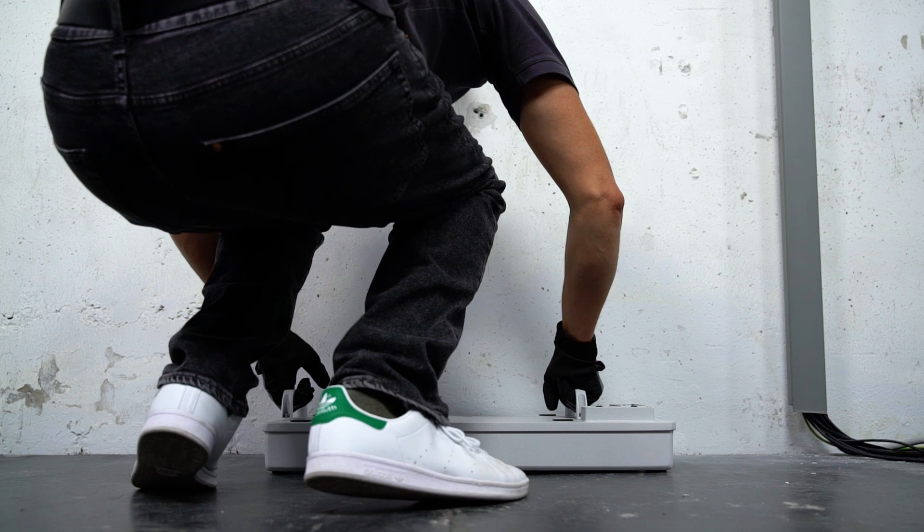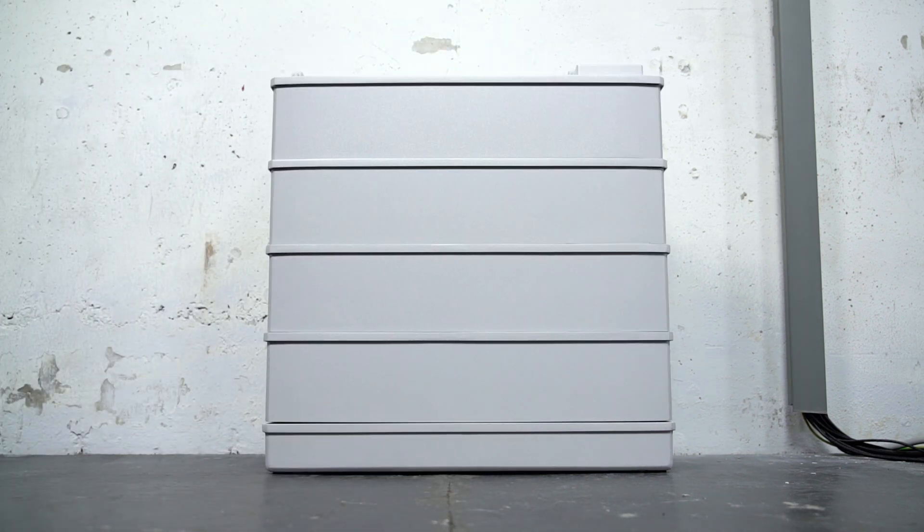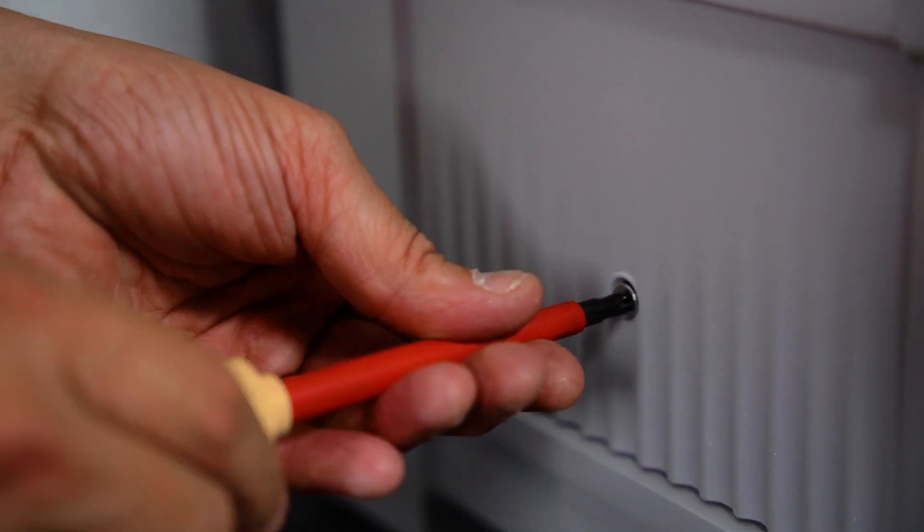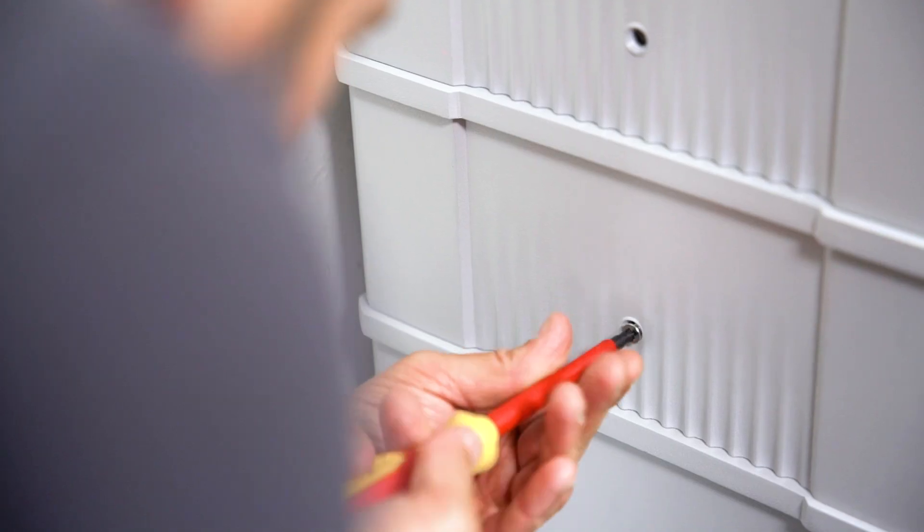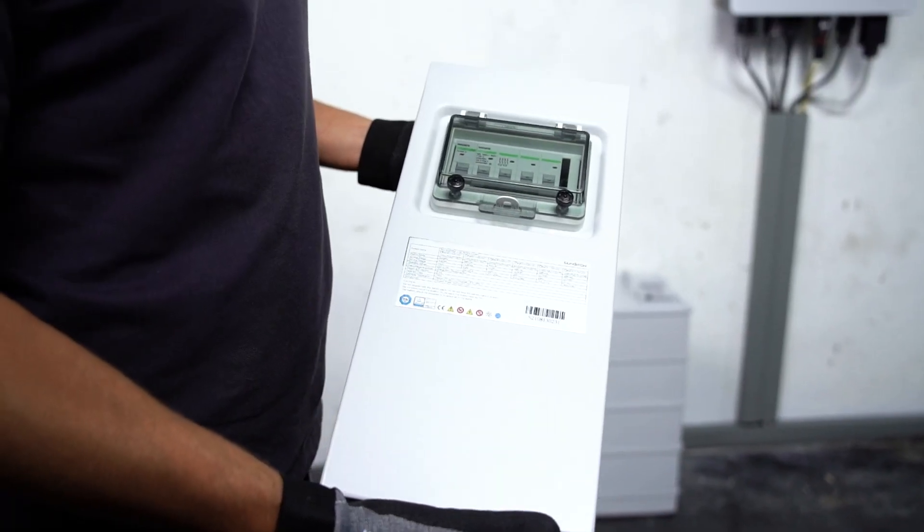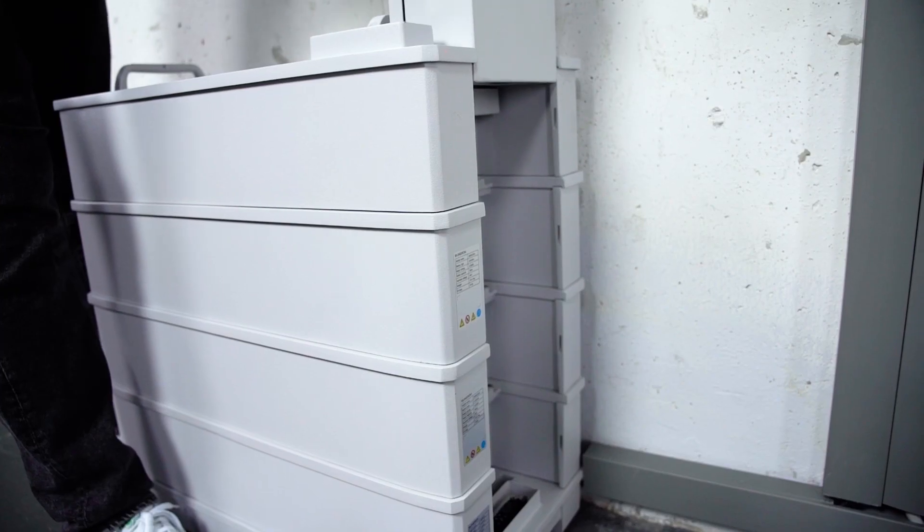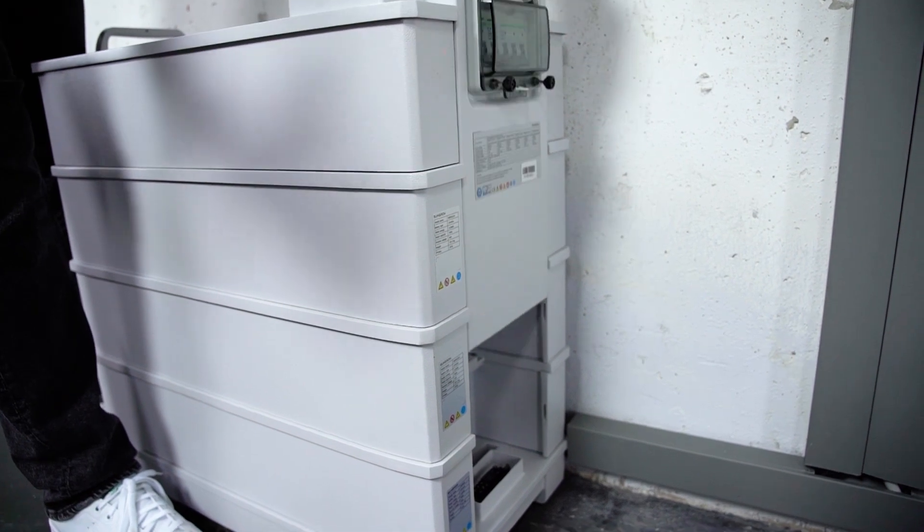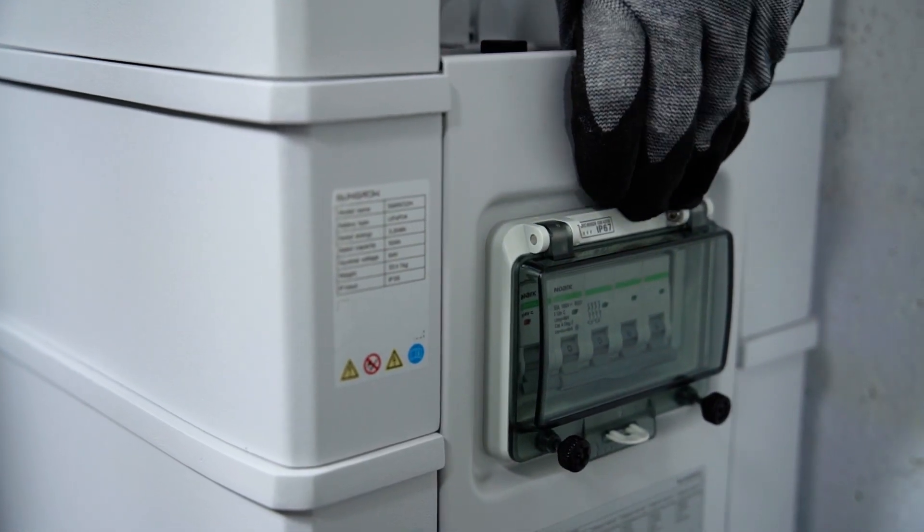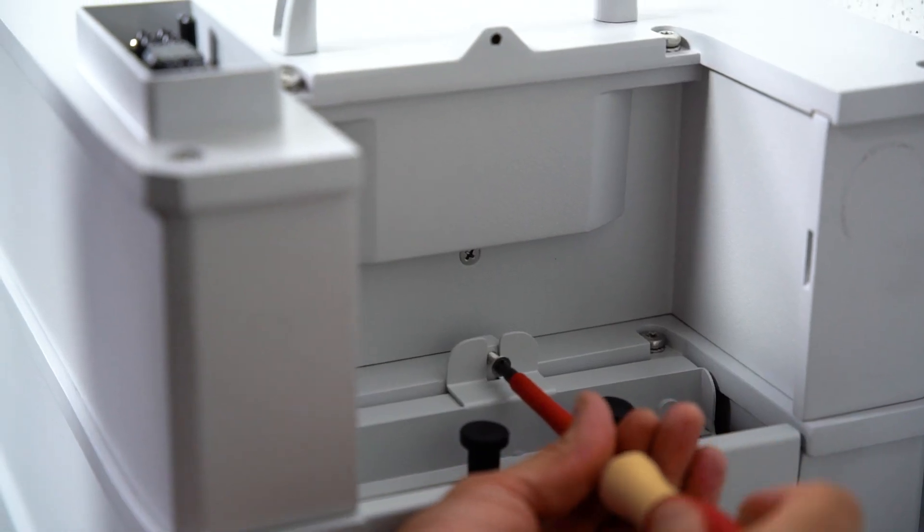With 33 kg, the individual modules are easy to handle. They are designed to be installed in a simple plug-and-play style. Fix the modules on both sides with the included M5 screws. Next step is to connect the switchgear to the base. Slide it into the foreseen slot on the right side of the battery and fix it with the included M5 screw.